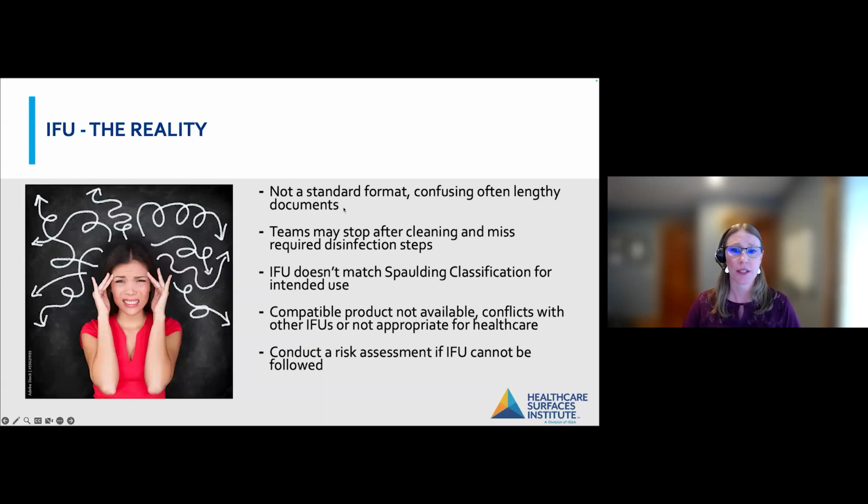Additionally, a lot of the documents are very lengthy. They can be hundreds of pages long. And so when you're trying to drill down to where's my cleaning and disinfection elements, that can be challenging to find. And when you have such a big document like that, sometimes the team may stop after the cleaning instructions because there's just too many steps that they get confused and don't even realize that they haven't gotten to the disinfection steps. And that's something that's really important when you're thinking about disinfection: the item has to be cleaned. You have to remove that visible soil before you can move to the disinfection step. And so if we do not follow the disinfection step, then we're not rendering that product or a piece of equipment safe for the patient.